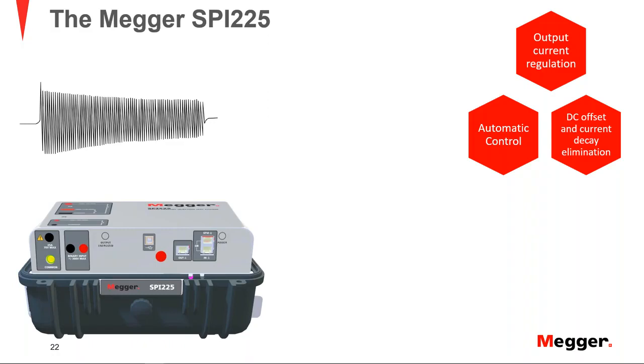We're going to heat not only the circuit breaker, the conductor elements in the circuit breaker, but also the leads that I'm using for the test. So we will see something like I'm just showing you right now, that curve depicting the current. The current will decrease since we are heating the conductors, including the test cables, as well as the breaker under test. So this is something that always happens.